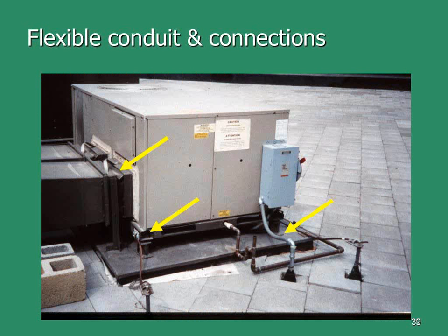It is in many cases, but as you come out of the air handler and the air is tumbling and turbulent coming down here, it makes the duct wall vibrate. If it's a critical situation, like the radio studio you and I worked on last year, we're not going to just depend on the fabric flex connection between the first duct and the air handler cabinet. We're going to make the first 2 or 3 hangers isolators, because there's always a little bit of residual turbulence and a little bit of residual noise, and so those duct walls are actually vibrating.